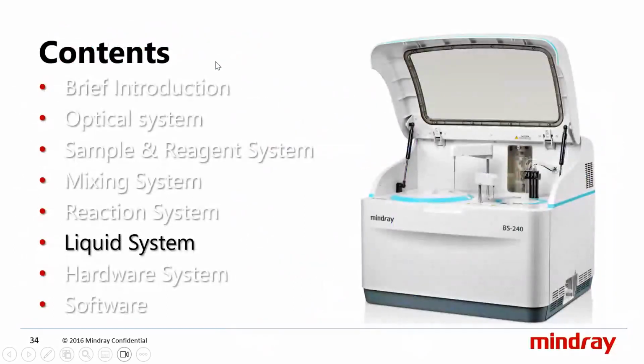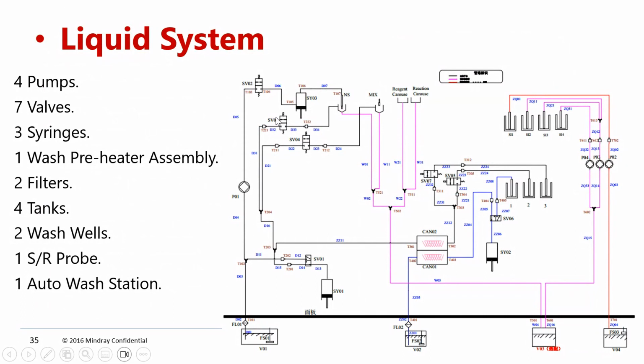So coming to the liquid system, unlike hematology, this tubing diagram is very easy. This tubing diagram is comparatively very simple and easy to understand. So we are using 4 pumps here in this analyzer, P01, 02, 03, 04, and 7 valves. The entire instrument has only 7 valves.